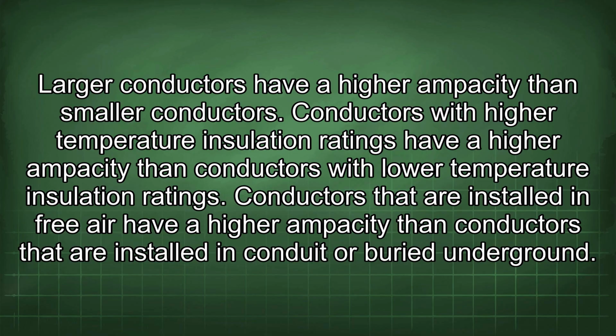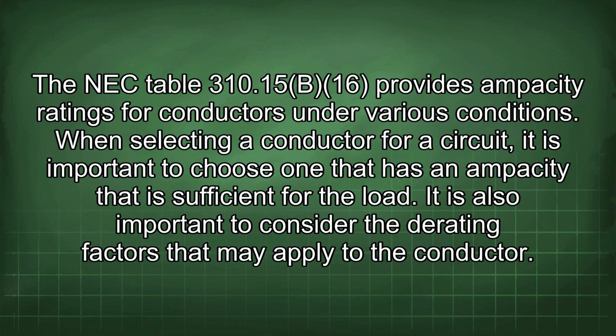Conductors with higher temperature insulation ratings have a higher ampacity than conductors with lower temperature insulation ratings. Conductors that are installed in free air have a higher ampacity than conductors that are installed in conduit or buried underground. The NEC Table 310.15(B)(16) provides ampacity ratings for conductors under various conditions. When selecting a conductor for a circuit, it is important to choose one that has an ampacity that is sufficient for the load.